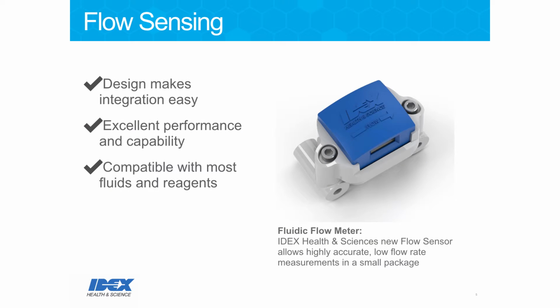Next up, we have our flow sensor. We're also pretty excited about this sensor. Like the pressure sensor, it is designed in a modular fashion, so you can either connect to it using tubing and fittings, or you can mount it on a manifold for a higher volume application, for example. What the flow sensor does is it gives an output in microliters per minute. This flow sensor is capable of measuring up to 1,000 microliters per minute in both directions, and the accuracy is about 5% of the reading.